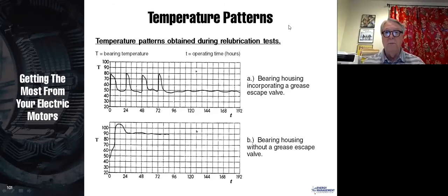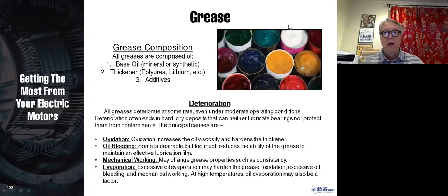You notice here in the top graph, this is not something you would do, but they lubricated every 24 hours. And so they lubricated, then 24 hours, they lubricated again, another 24 hours, lubricated again, and at 72 lubricated again. This is not a proper way to lubricate, but it's good for a test. And you can see how when they put the lubrication in, the temperature goes up because that bearing is packed full of grease, and then it comes back down to its normal operating temperature. So that's kind of a pattern that you should see when you lubricate your motor. Grease composition.